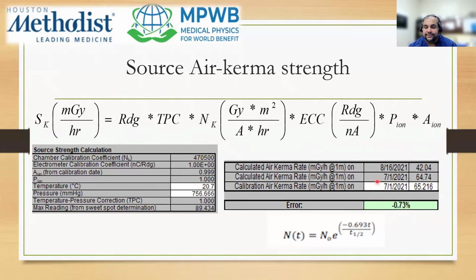So for instance, in this scenario, what we're trying to calculate is your N0. So N is 42.04, which equals N0 e to the minus 0.693 T, where T is the number of days that have elapsed from the day the source was manufactured to the day you're doing the source exchange, divided by the half-life. Finally, you calculate the percent error between the two air kerma strengths, and that number should ideally be less than 3%.